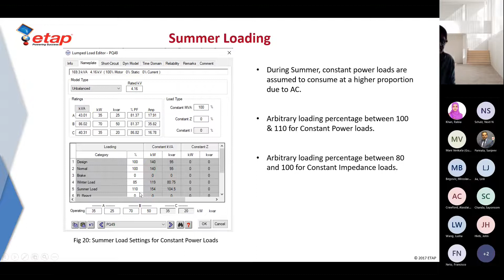Here I have taken an example where I've considered the scenario to be summer, and in summer settings I have assumed constant power loads to consume a higher proportion than constant impedance loads because of air conditioning requirements. These are the settings where you can see rows 4 and 5. I have altered the percentage for summer and winter to account for that. And here it's winter loading. For winter loading, I have assumed a higher contribution from constant impedance and constant current loads, because lighting loads tend to dominate compared to air conditioning loads, and heating is often gas. So the winter loads for constant impedance take up a higher percentage.